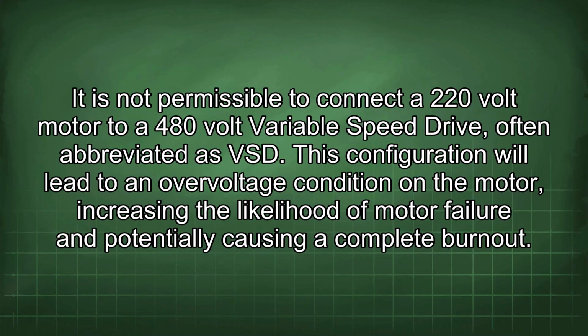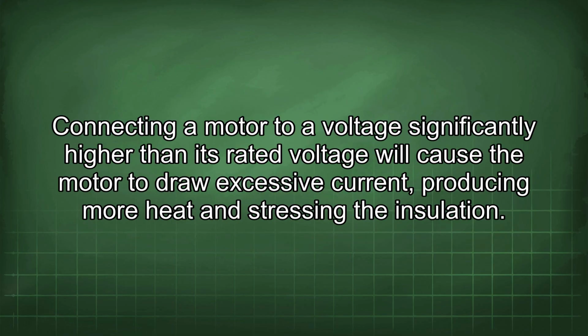It is not permissible to connect a 220-volt motor to a 480-volt variable speed drive, often abbreviated as VSD. This configuration will lead to an overvoltage condition on the motor, increasing the likelihood of motor failure and potentially causing a complete burnout. Connecting a motor to a voltage significantly higher than its rated voltage will cause the motor to draw excessive current, producing more heat and stressing the insulation.